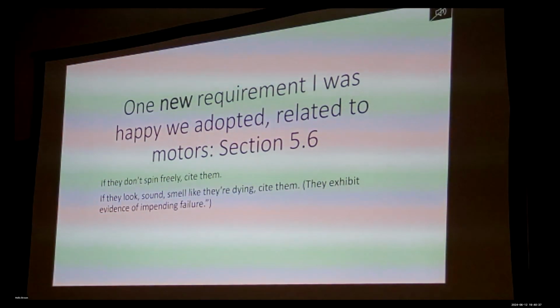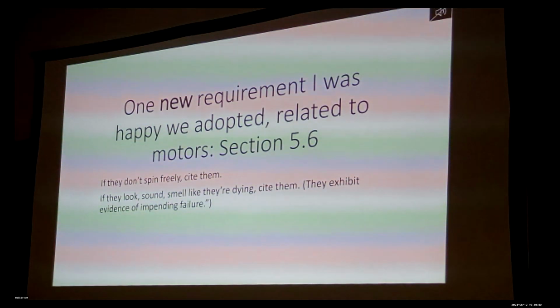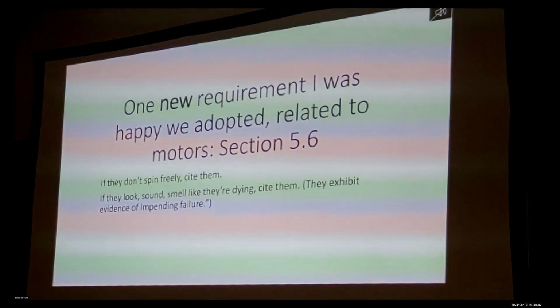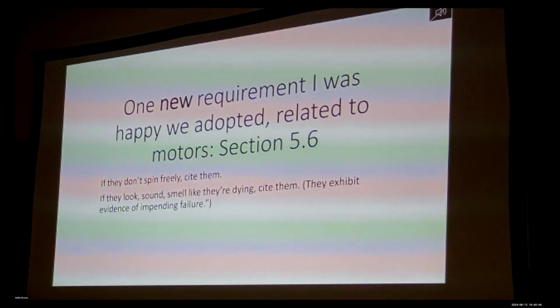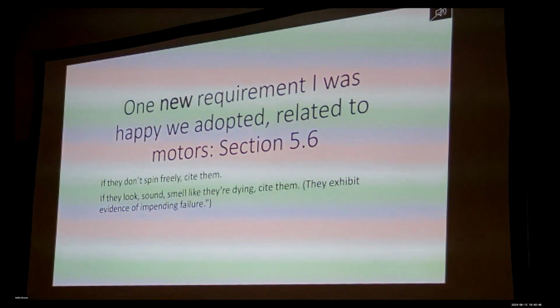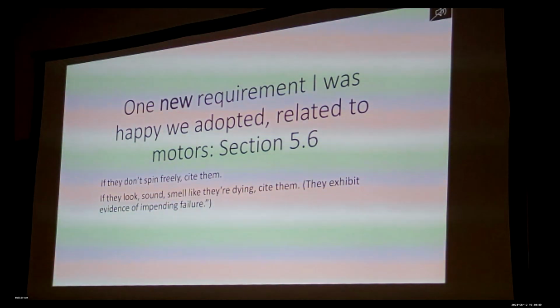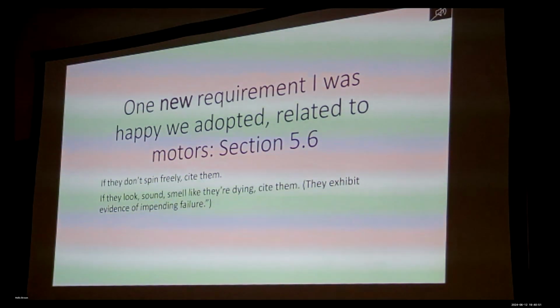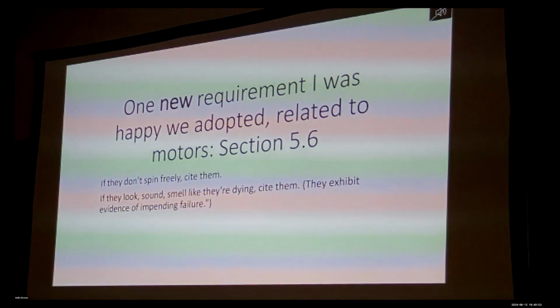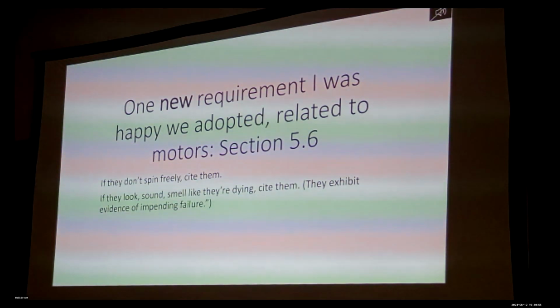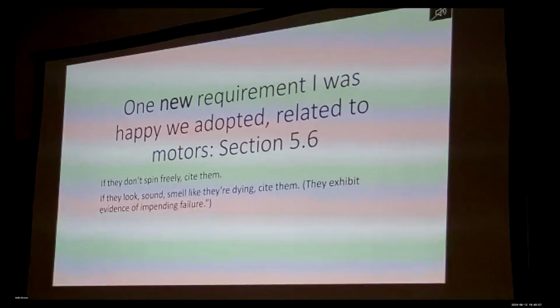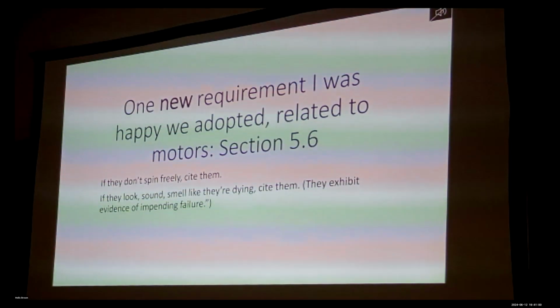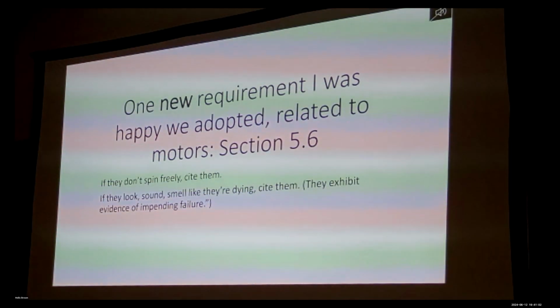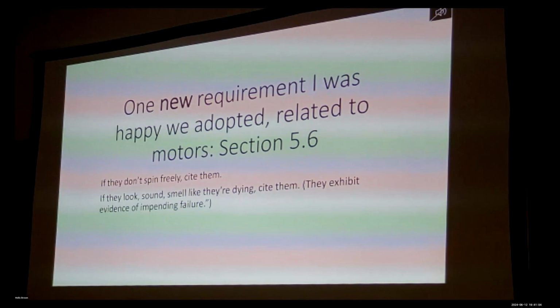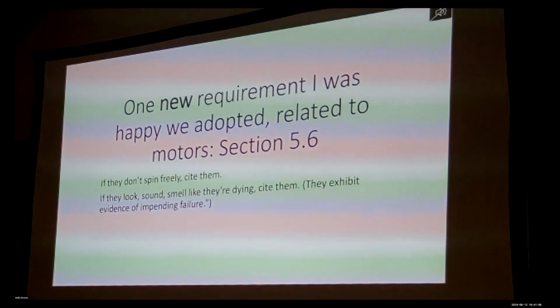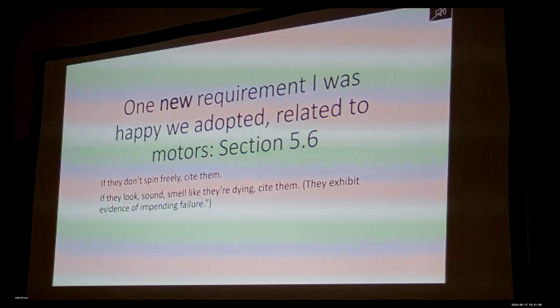We had to fight, or dicker, to get this new rule in, because what's the appropriate wording? Well, if a motor doesn't spin freely, you hope its thermal overload will kick in before it starts a fire, if it's correctly chosen and so forth. And even if it does, where's your customer, and where's the function that motor was supposed to be performing?